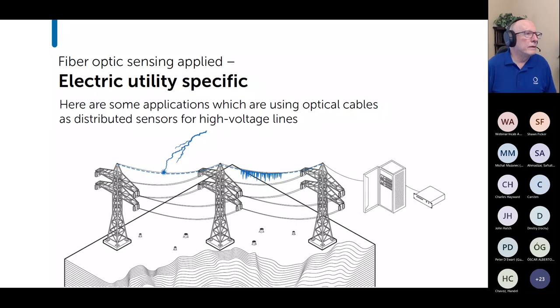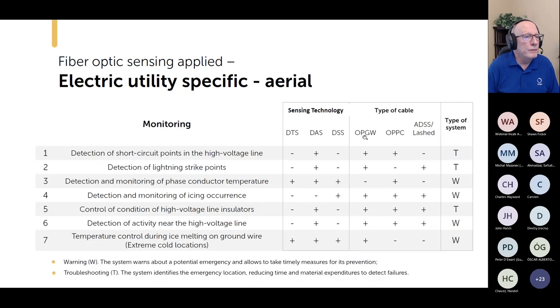So I'd like to come back to this theme of what electric utilities can do. Here's an overview, by sensing technology and by the type of cable that goes with it, and whether you're getting a troubleshooting system, where the system is identifying an emergency location, telling you exactly where you need to go right away to get something fixed, or just a warning that's telling you something bad is about to happen and allows you to head that off. So you can already detect short circuit points on a high voltage line. Now, somebody could say, well, the relay and control system can do that too. And I would say, yeah, that's true. But potentially with OPGW, and you can do that with OPGW or OPPC, but I do believe the accuracy of the OPGW approach would be better.